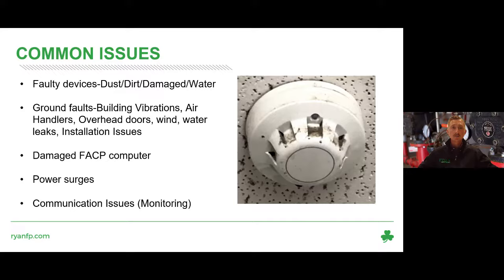Buildings vibrate, the land, the environment vibrates. Sometimes air handlers on the roof will vibrate and cause a ground fault. Overhead doors going up and down in big distribution warehouses, wind, water leaks, roof leaks, or again cleaning crews, sanitation crews, hitting water on devices or wiring and making it touch the building.